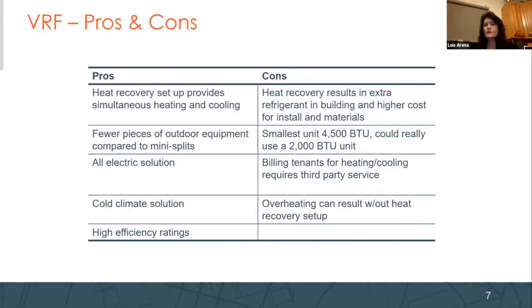Okay, so here's some high level pros and cons. I just tried to throw some out there. There's much more to it than this. We're going to go down the pro side first. Heat recovery, and I'm going to show you what that looks like, is setting up the system in a way where if I'm really cold in my apartment, I can run heating, but if my neighbors or somebody on the same floor is on the south side and they need cooling, they can run cooling at the same time, okay?